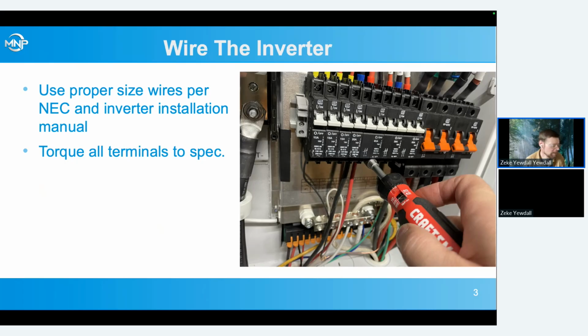One thing to note on these particular terminals that we have on the breakers is they are a box terminal that sometimes looks like it's ready for a wire to go in there when they're fully tightened, and they come from the factory fully tightened, so they don't rattle loose. So you've got to make sure you open them up and you'll see that box kind of move down and actually open up to put a wire in there. We've had some people comment that it seemed like they had to turn the screw counterclockwise to tighten on the wire, which means it's trapped between the plastic and the bottom of the wiring box, not in the actual box that's supposed to be clamping the wire. So just something to be aware of on these breakers.